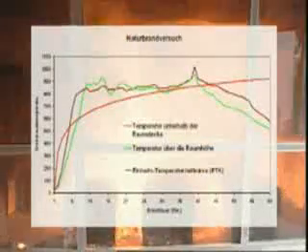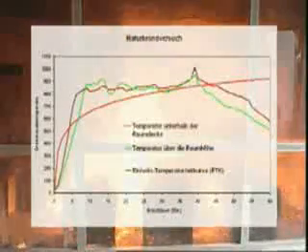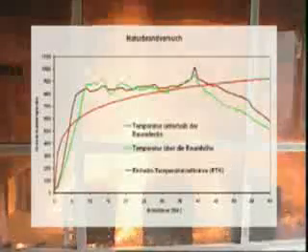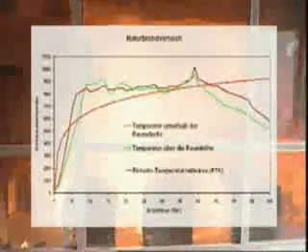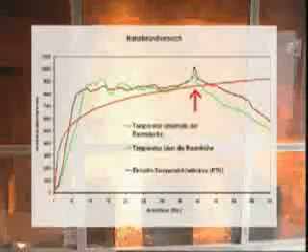By the 41st minute, the temperatures of this fire under natural conditions reached much higher values than those under standard testing conditions in the material testing facilities. The highest temperature was recorded in the 38th minute. The fire protection system's functioning has been proven in this original fire. It is safe to say that the systems can be recommended for use.